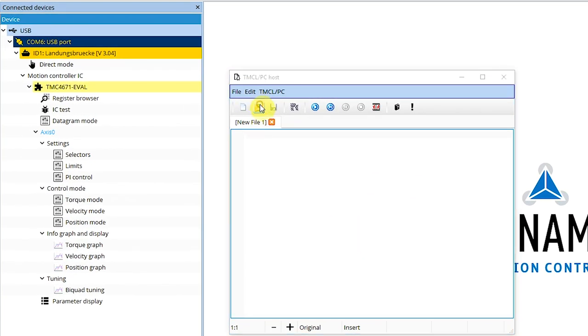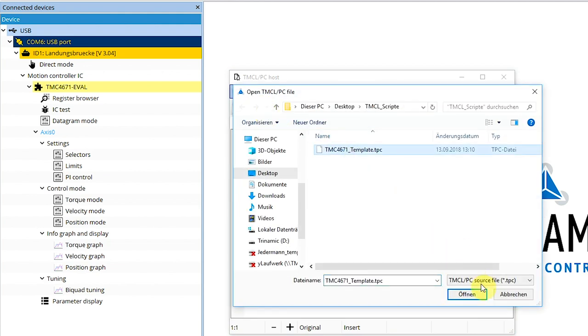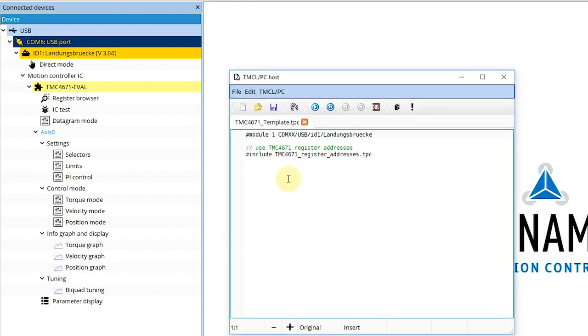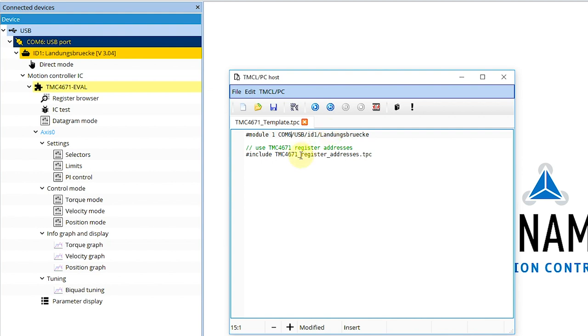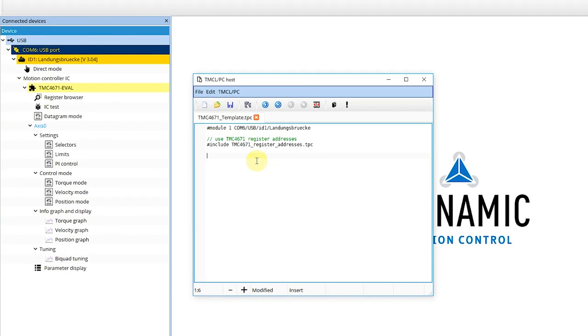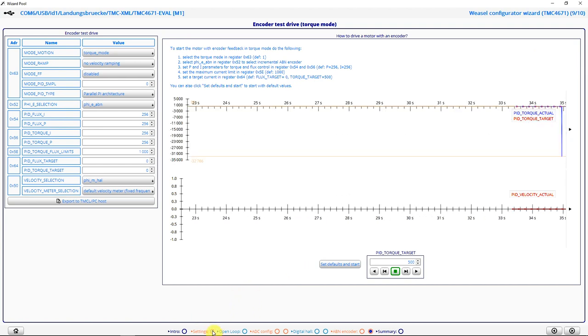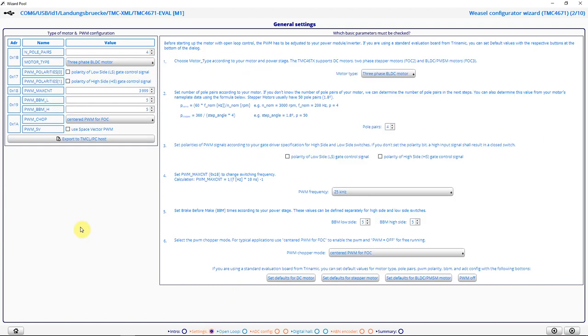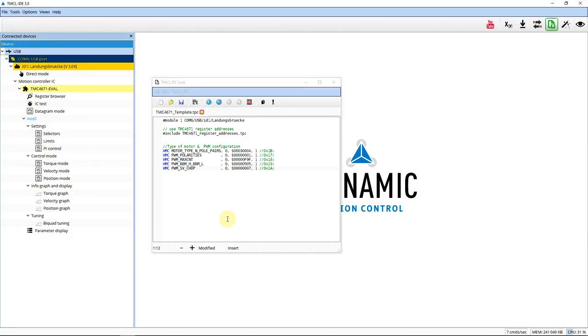Here I open my template file. And I see here which module I want to use. I have to put in the correct COM port. So it's COM6. And I include a header file containing all addresses of the TMC4671 registers. I go back to the wizard and go to the first dialog. Here I see the button export to TMCL PC host. I click this and I close the wizard again. And I see now that the registers I configured in the wizard are now here in the TMCL PC script.